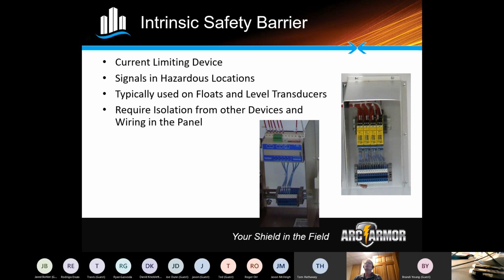Moving on to intrinsic safety barriers. We touched a little bit on this, but what's the purpose of intrinsic safety barriers? Intrinsic safety barriers are designed to protect equipment that is installed in what they call a hazardous location. So in our industry, municipal water and wastewater, hazardous locations are going to be lift station wet wells, headworks buildings in plants, and other areas that can be classified within a plant as hazardous.